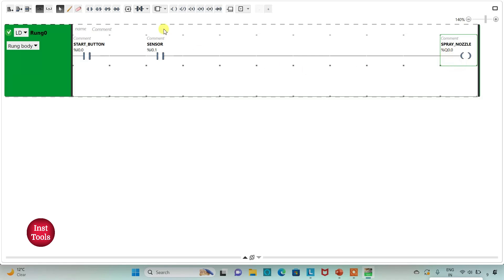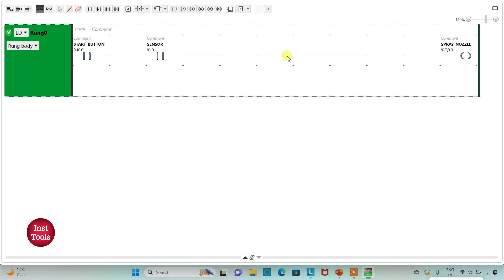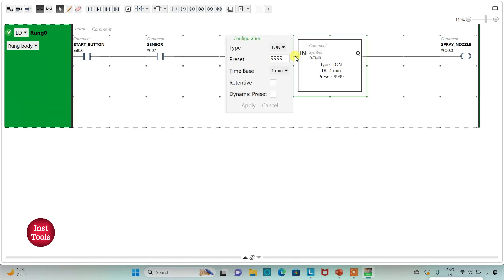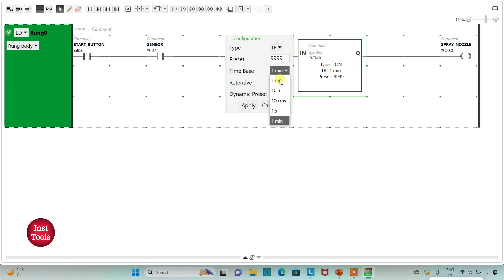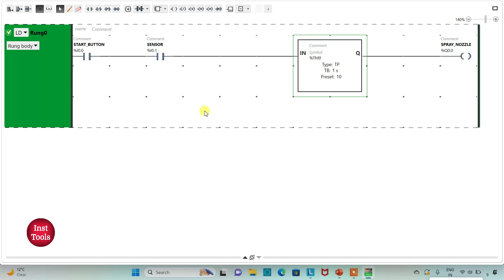This spraying process should occur for 10 seconds. For that I will use a timer, and that should be a pulse timer — TP. I will change the time base to one second and the preset value to 10, then click Apply.